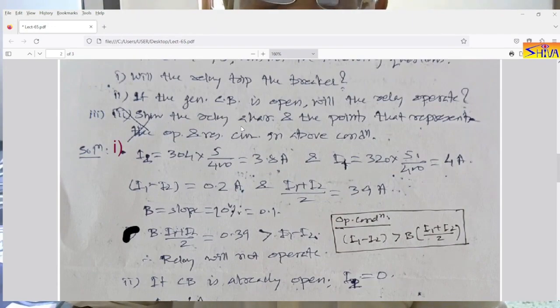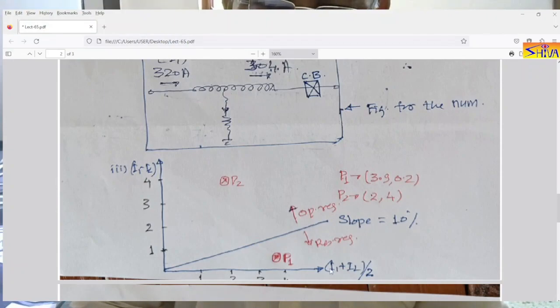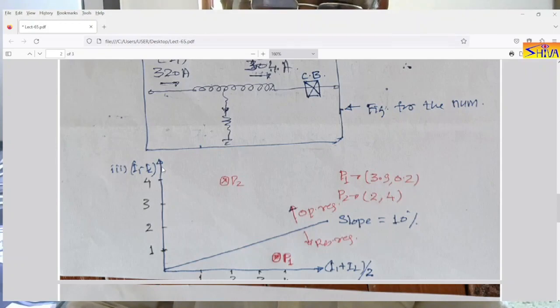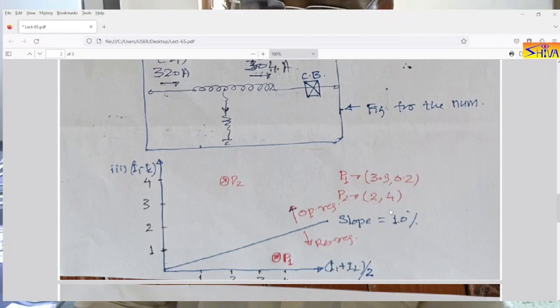The third part asks to show the relay characteristic and the points representing operating and restraining current. For the percentage differential relay, we plot the mean circulating current (I1 + I2) / 2 along the x-axis and the differential current (I1 − I2) along the y-axis, using similar scales on both axes. The slope is 10%, so drawing a line at tan⁻¹(0.1) ≈ 5 degrees with respect to the x-axis defines the characteristic.